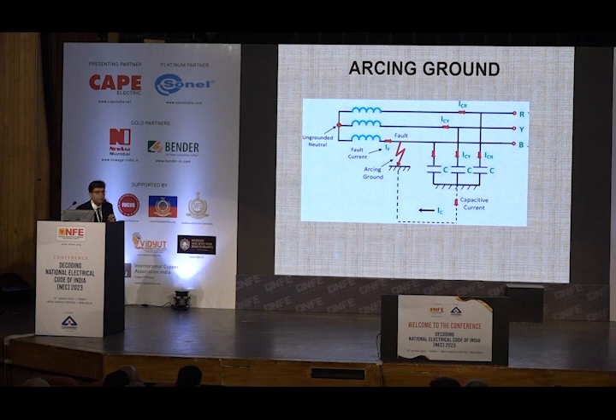Arcing ground is a phenomenon when the voltage of your healthy phases becomes high, more than the system voltage, equal to the system voltage for a fault in one phase with respect to earth, SLG, single line to ground fault. And that makes your gadgets in the houses fail. In short, opening of your earth connection at the distribution transformer causes this kind of incident.